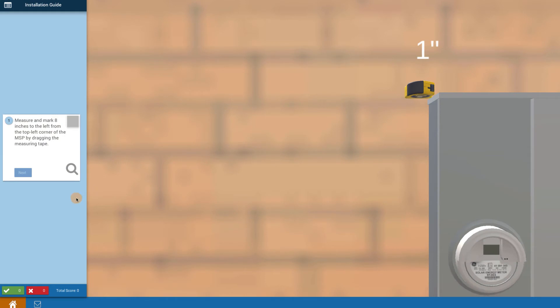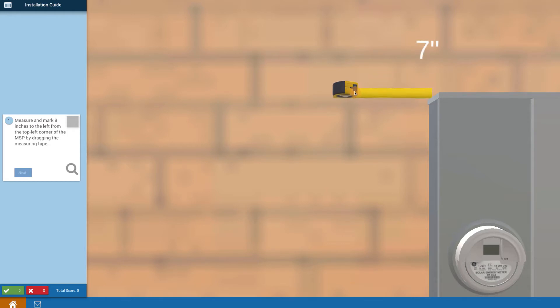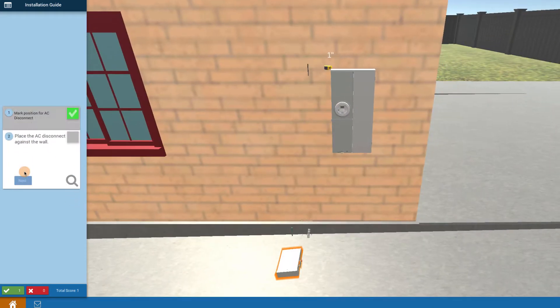This is how we're going to go through the steps of mounting the AC disconnect. It says to measure and mark 8 inches to the left of the top corner of the main service panel. So you press down on your tape measure tool, drag it across and measure out until you get 8 inches separation. Then let go and it draws a mark for you. That's the first step.